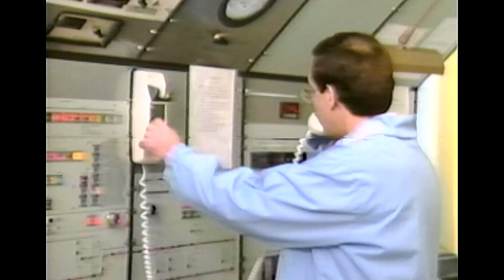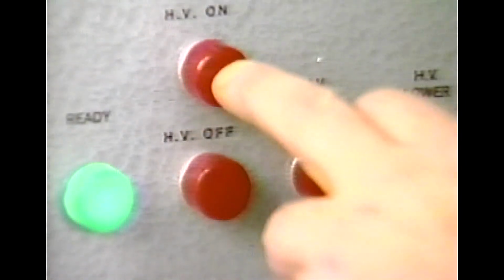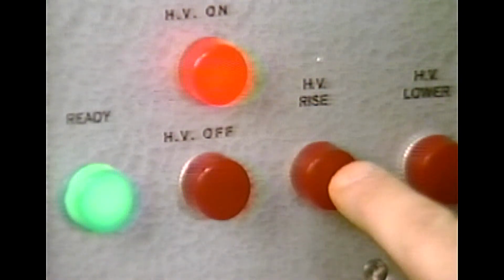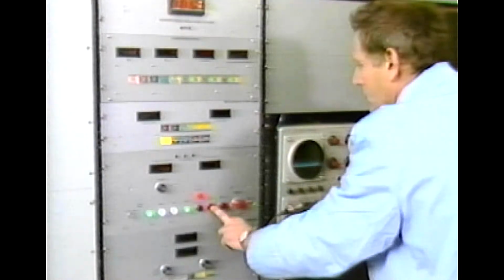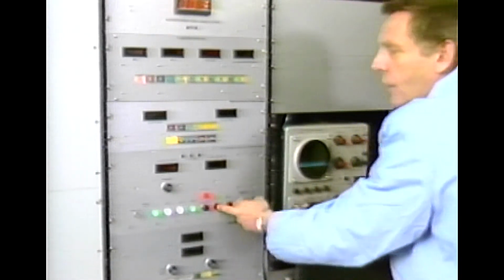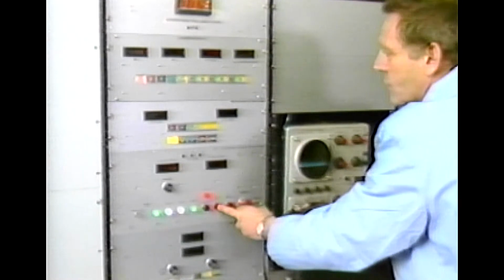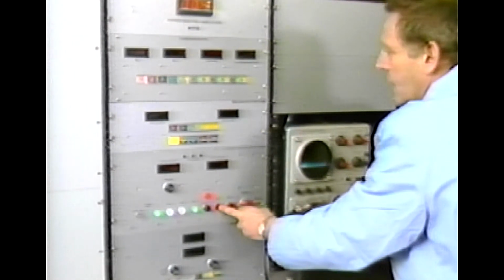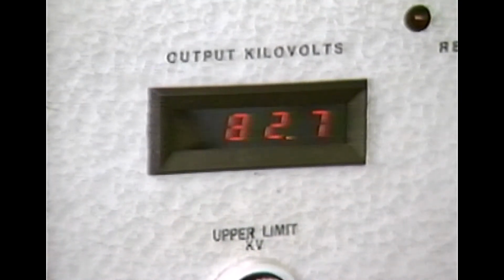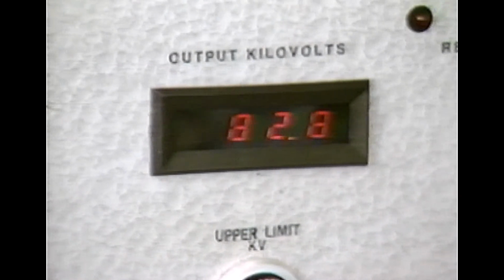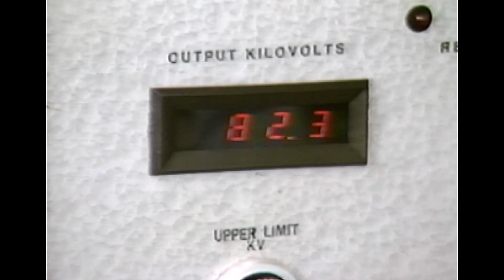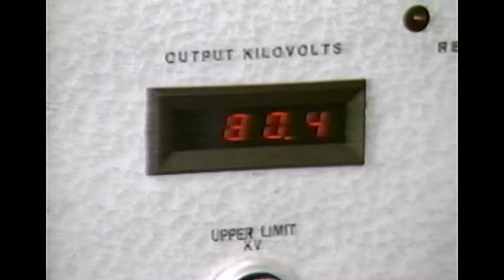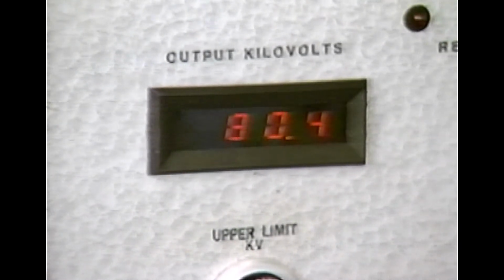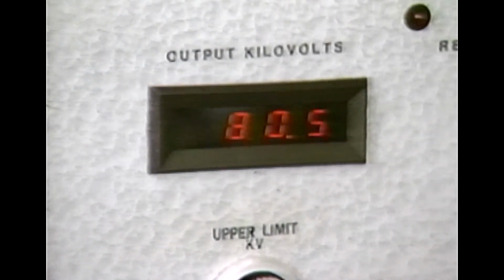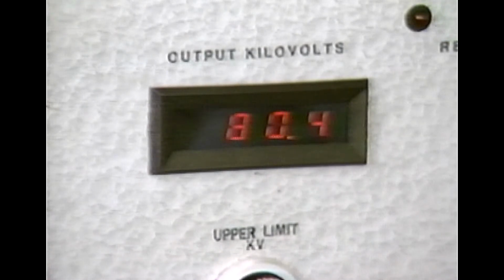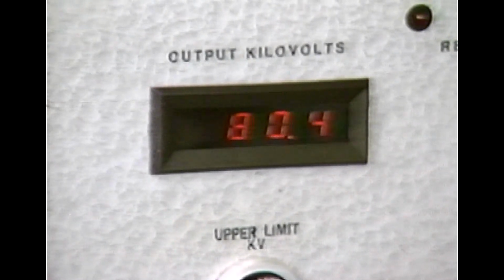High voltage on. High voltage is applied first and the cable performance checked up to the rated level of 80,000 volts, single phase. Now up to 50 kV, 60. Okay, we got voltage on the line. 80 kV, 80.4 as a reading. Partial discharge, no change.